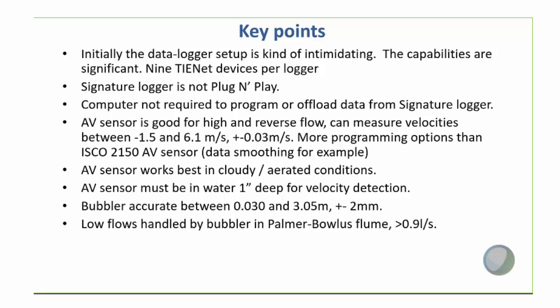The AV sensor is good for both high and reverse flow, as Jane talked about. We have measured that. We have seen negative velocities as well when a ditch will fill up and we'll get water going back into a pipe. So the AV sensor, again, works best in cloudy and aerated conditions, but we've got some pretty clear systems, and we feel like we're getting some pretty reliable data from that as well. We do have to have 1 inch of water in order to get a reliable velocity reading, which means we're eliminating all those low flows. So that is one drawback.